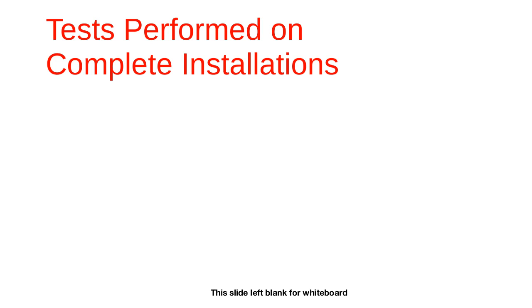So when you're carrying out this visual inspection, you should be able to ascertain that the correct size of cables has been used. Because you see, if an installer uses, let's say, a 1.5 cable for a heavy power final circuit such as the cooker, that means that installation generally is not safe.